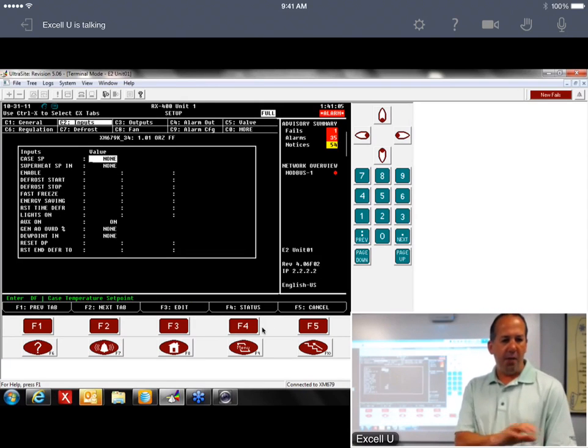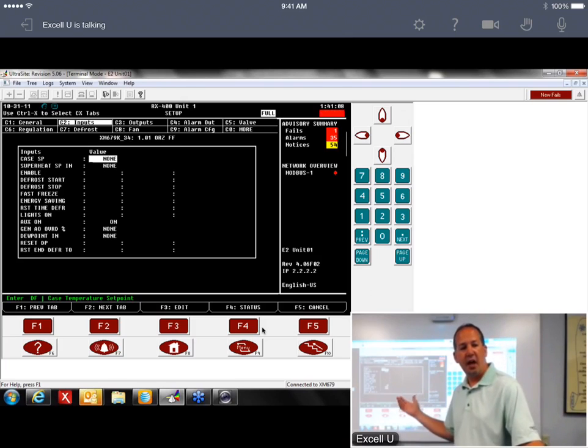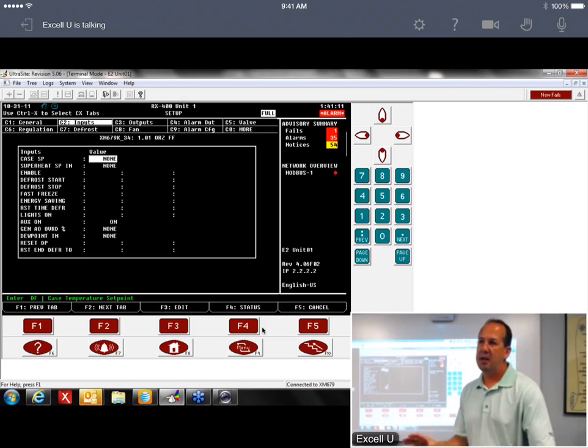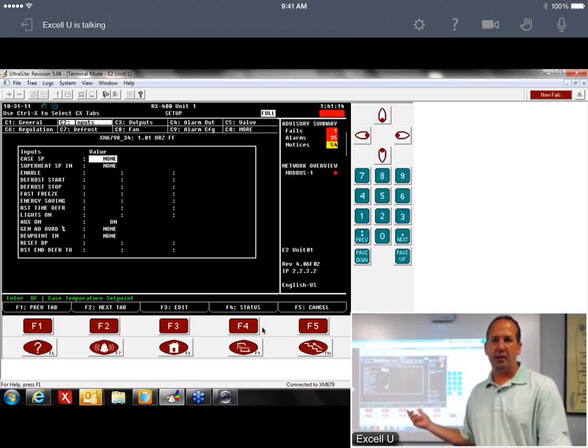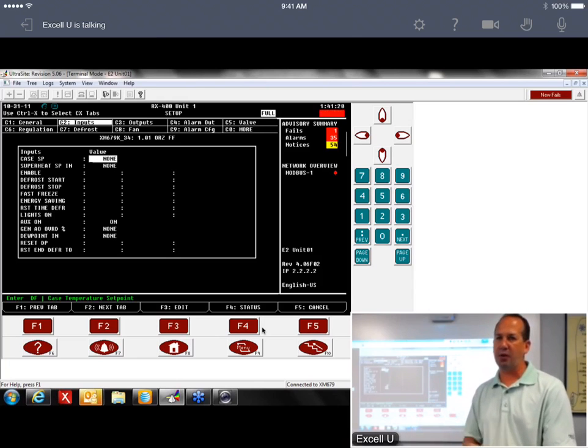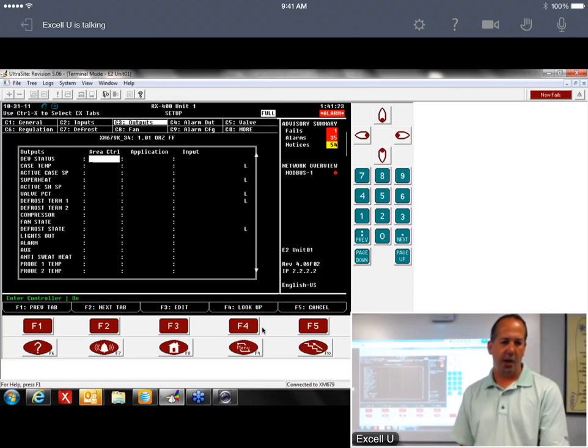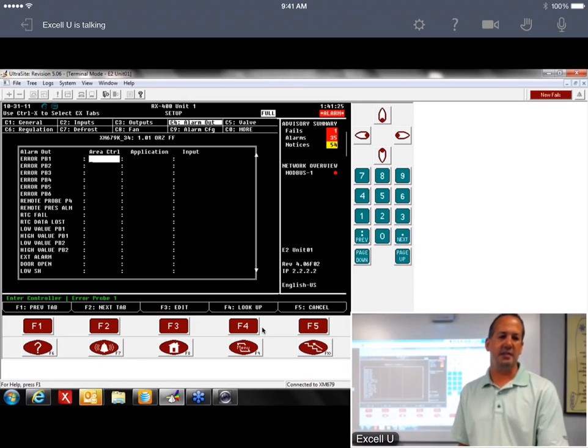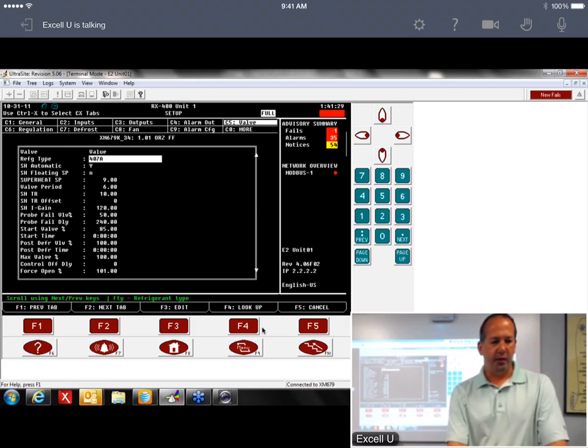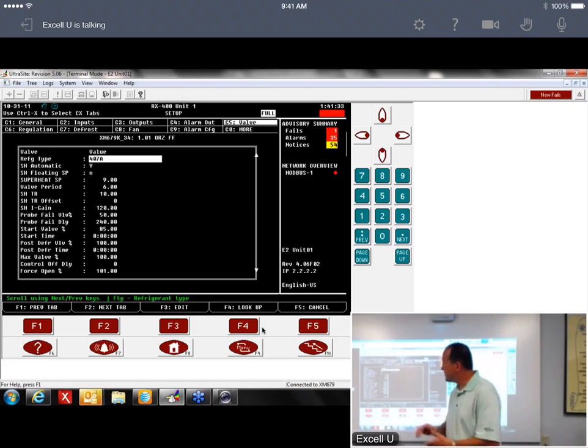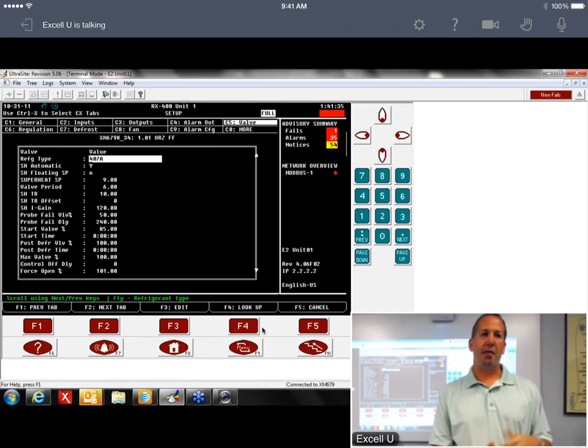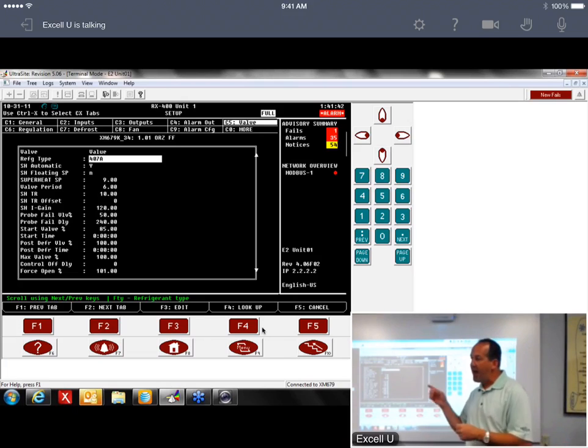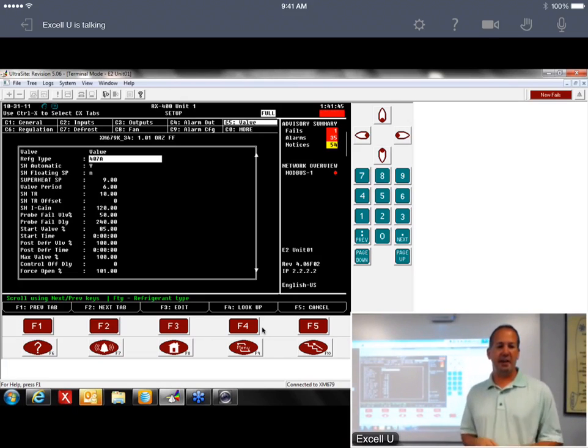Most of this, in the XM device, it's got all the parameters in it, and it's going to get a lot of this information from the XM circuit. So there's not a whole lot that we do in this device setup, because once we associate it to the XM circuit, it's going to fill in all this stuff for us. So I just want to hit the high points of what we need to look at changing. The valve tab, the refrigerant type, is defaulted at 404A. I think we're all using 407A. You might have 404A on some of your remodels, but that has to be changed. So whenever you set this device up, make sure you set your refrigerant type.